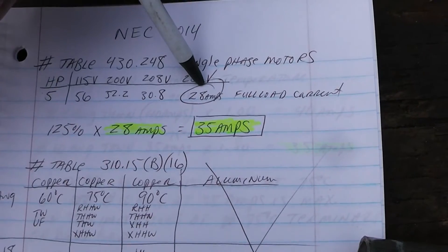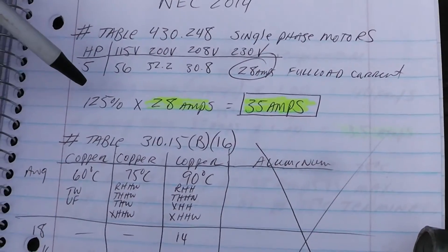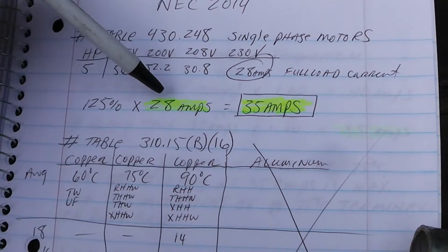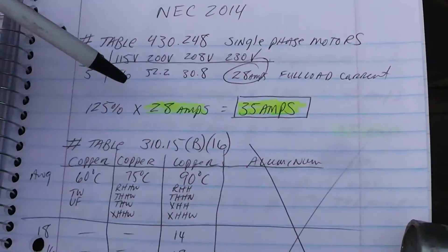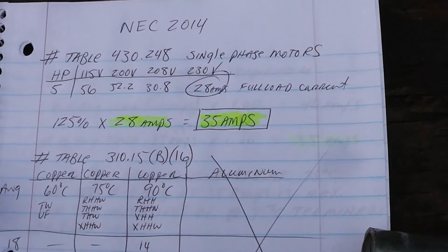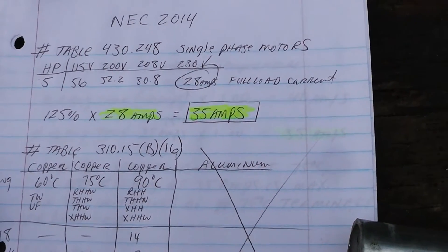That's what you have to size the conductor or the wire to - that's the full load current. To find the size of the conductor, we multiply the full load current, which is 28, by 125 percent, and that gives us exactly 35 amps.